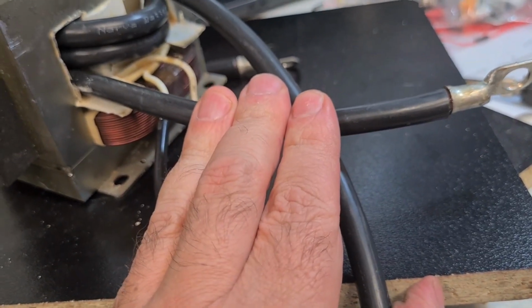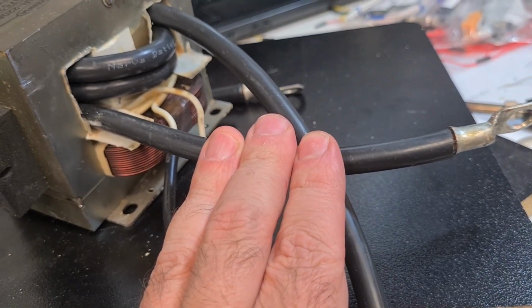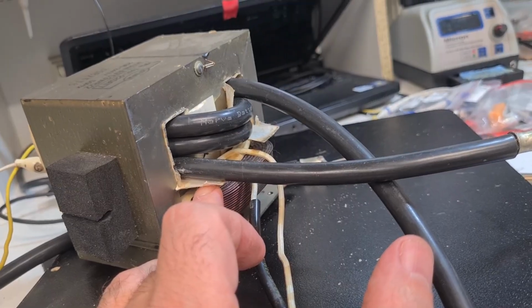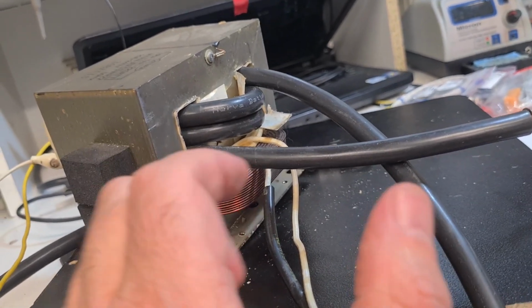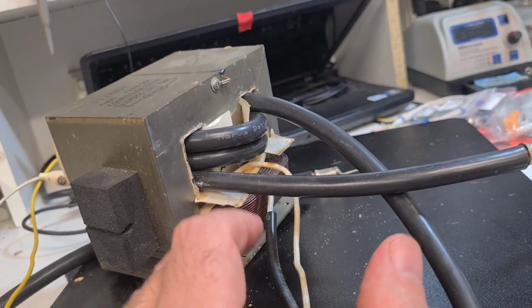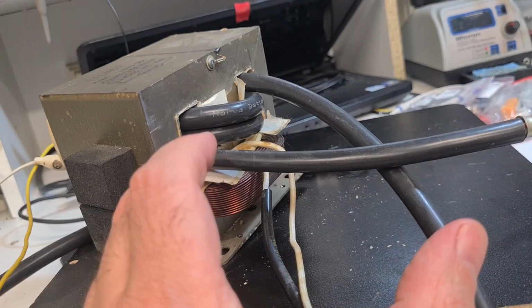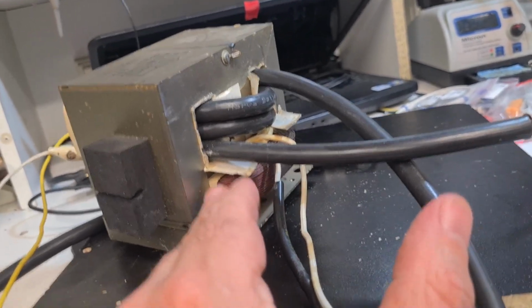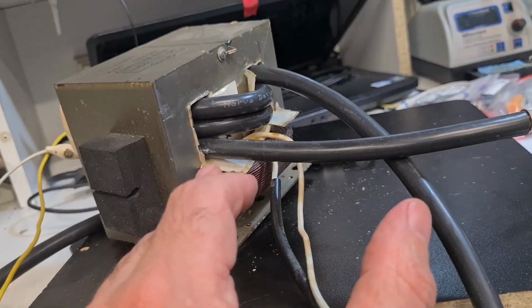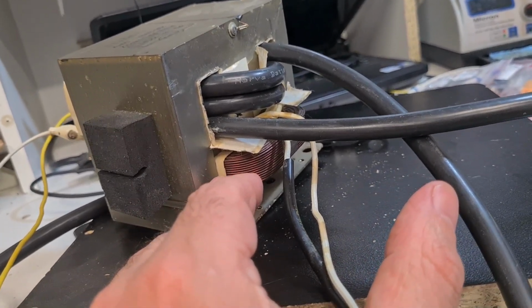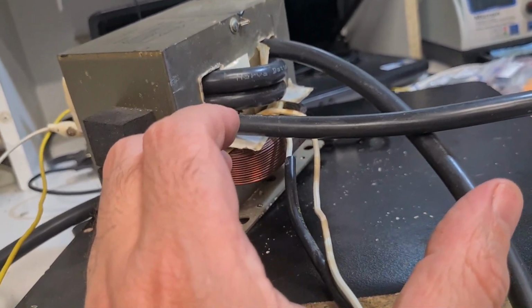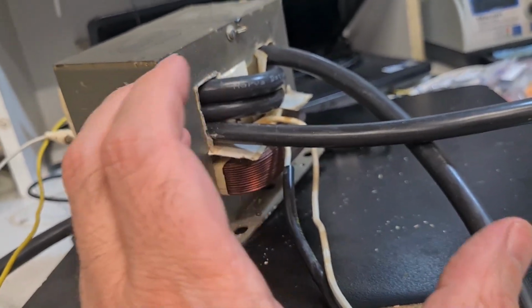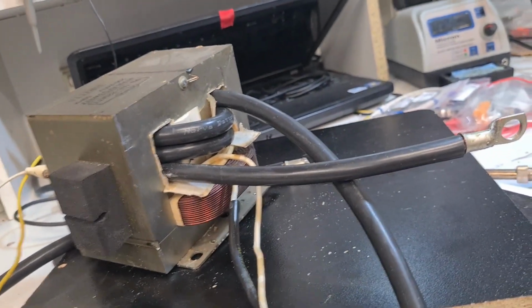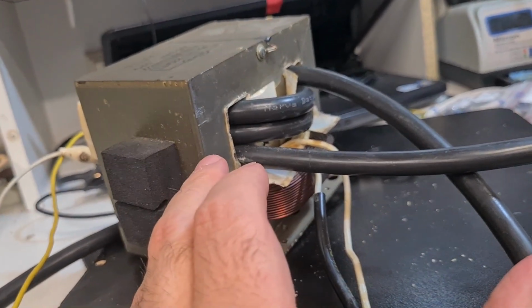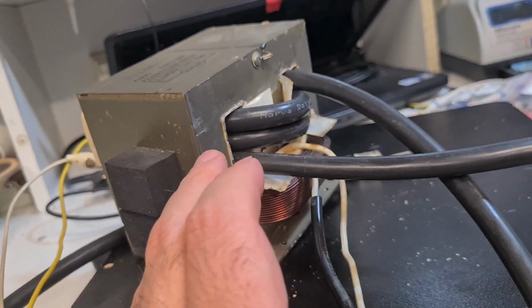And with the shunts on, it will limit the high currents. It won't let the secondary take too much power, and therefore as well the primary will be limited as well, because then the whole transformer is already running saturated. So the magnetic field, the magnetic core, the flux of the magnetic fields is saturated. Therefore, it's like it hit its limit.